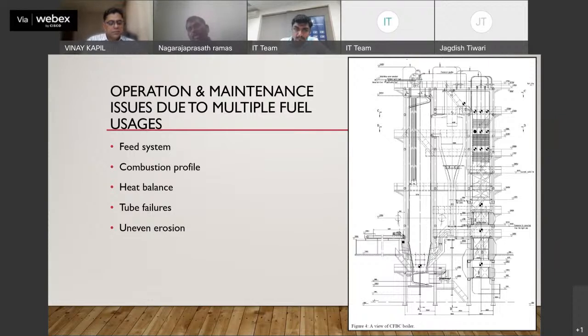In terms of the combustion profile, after using biomass, the temperature profile in the furnace was entirely different compared with coal. When we fire coal, the difference between the bed temperature at the bottom and the furnace top temperature is very small, around 30 to 40 degrees Celsius. When we fire more husk, it completely burns at the top of the furnace, so there is a much larger difference between the top temperature and bottom temperature, around 100 to 120 degrees Celsius. After modifying the cyclone, it was reduced to between 70 and 80 degrees Celsius, but still the temperature difference is there.